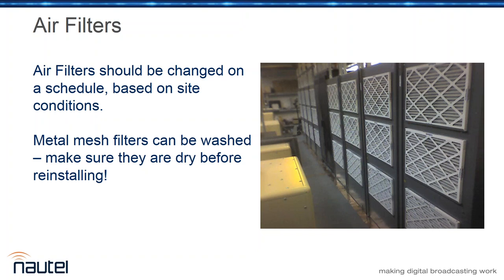If you've got metal mesh filters on a piece of equipment, they can be taken out and washed, hosed out, taken to a car wash, a touchless car wash, whatever. If you do wash metal mesh filters, number one, be sure they're dry before you put them back in, so you don't blow water through the transmitter. Number two, a lot of metal mesh filters require filter coat, a gummy substance sprayed onto the filter media to allow them to attract and hold dust in the air. So if you have that type of filter, make sure you put the filter coat on them as well.